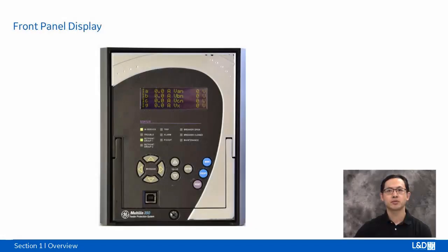On the front panel, 3 Series has a 4 lines by 20 characters LCD display, which allows visibility under varied lighting conditions. There are 10 or 12 color-coded LEDs to indicate the type of event. Below the LEDs, there is a 10 push-button keypad for access to the device, interrogation, change of settings, and control commands. At the bottom, a USB port allows the user to make a quick connection with Vista software.